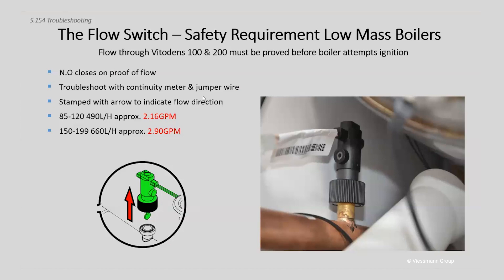The flow switch is essentially just a switch — a normally open switch that closes when we get the pump at the right flow rate. It's important to note there is a minimum flow rate on all flow switches — they don't know what your flow is except for that one position when we meet or exceed the minimum. The smaller boilers — the 120 and 85 — have a 2.16 gallon-per-minute flow switch regardless of model. You need at least 2.16 GPM before that flow switch will close. The bigger boilers need about 2.9 gallons per minute before the flow switch will close.